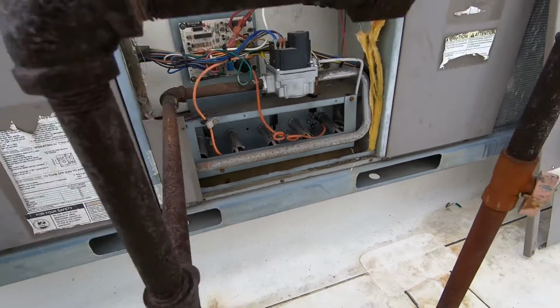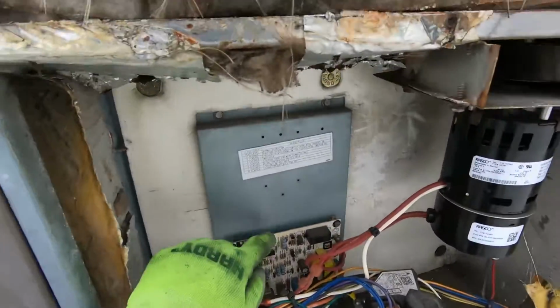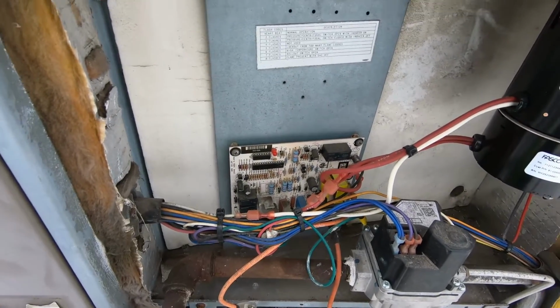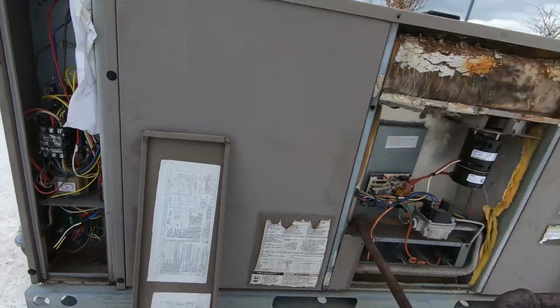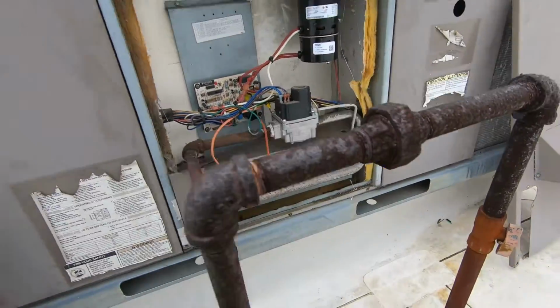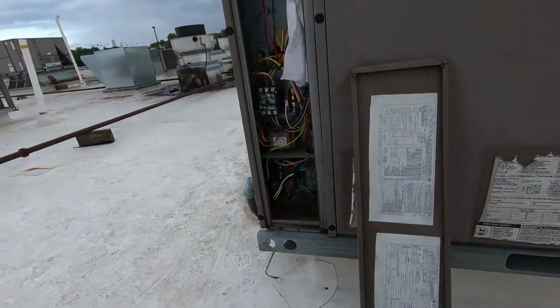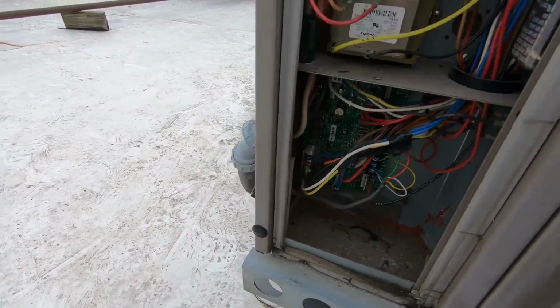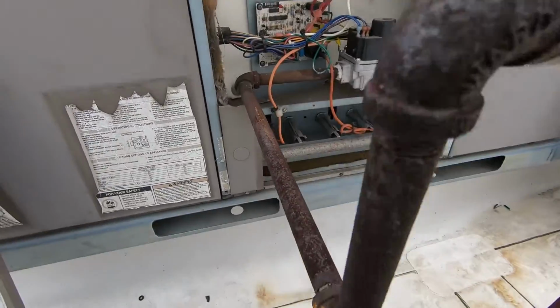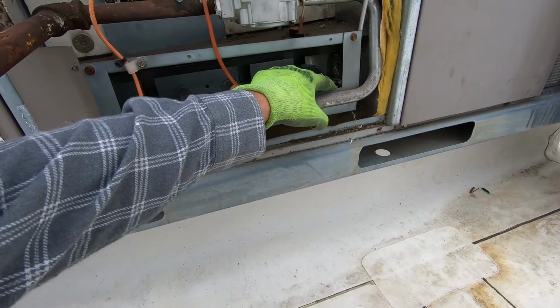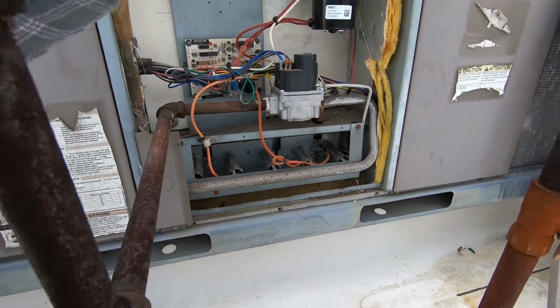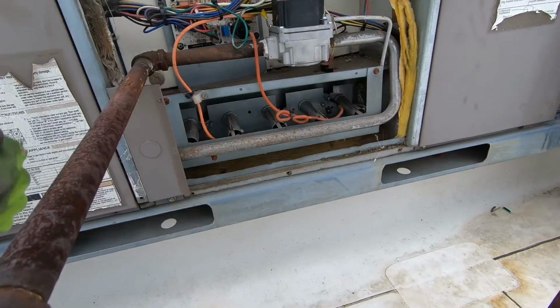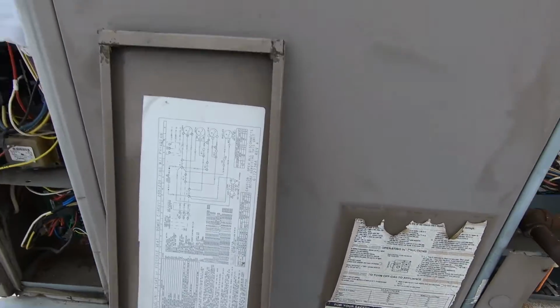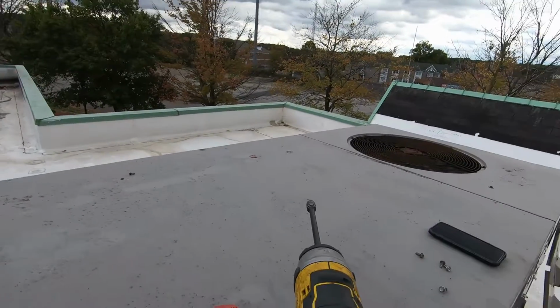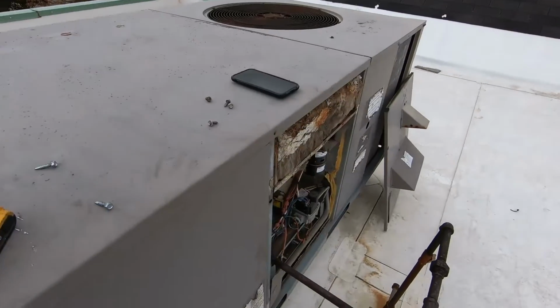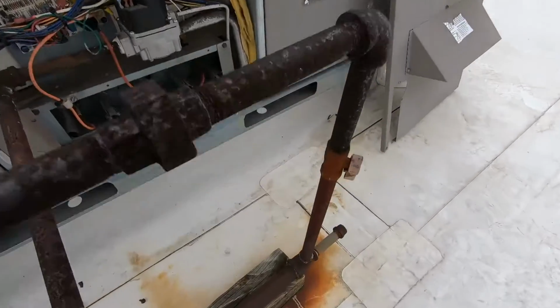Let's take a look at that one more time. What are we flashing over here? We're flashing normal. I heard the rollout switch trip there. I heard the rollout switch go ahead and shut. What we got here? We're flashing normal. It should come back on. I want to catch that on video, but this burner right here was rolling out. So I'm gonna have to go grab some pipe wrenches, shut this off. We're gonna pull all this out and inspect it. All right, here we go. Let's watch this again.